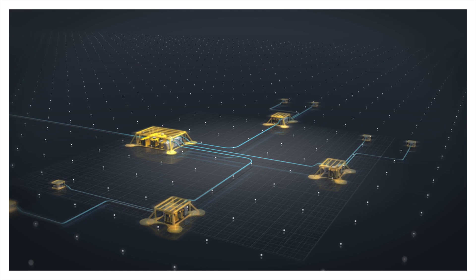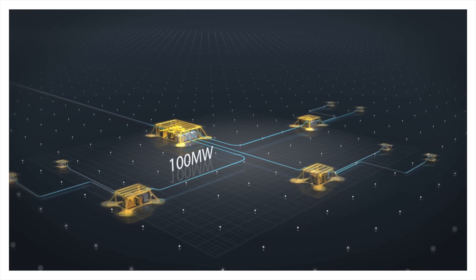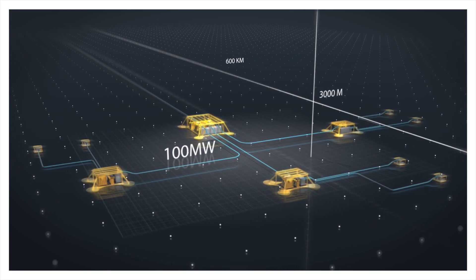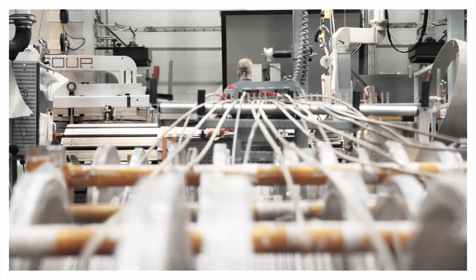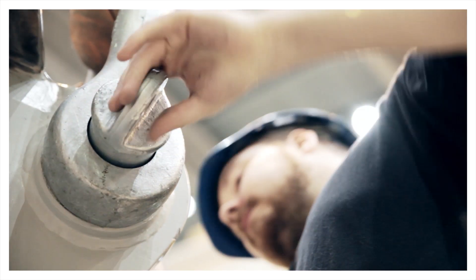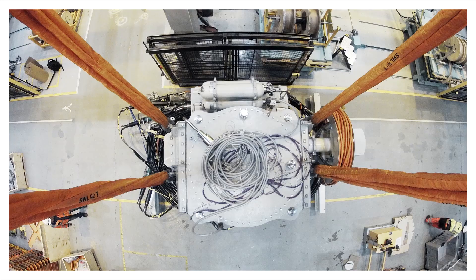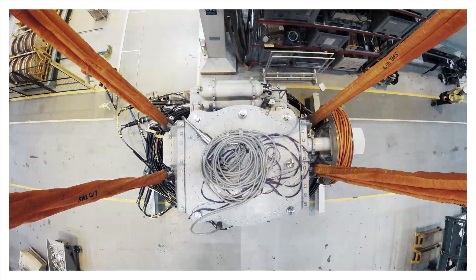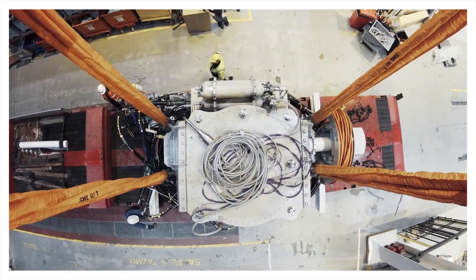Ultimately this technology can provide reliable power of up to 100 megawatts to depths of down to 3000 metres over distances of up to 600 kilometres. ABB entered the subsea market in the 1980s, leading to the delivery of the world's first subsea transformer in 1998. More than 20 subsea transformers have been delivered from ABB — a vast majority of the world's subsea transformers — and none have failed.